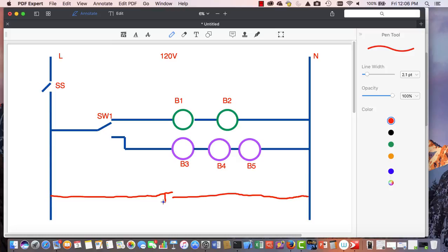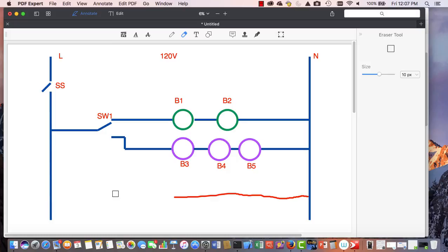that would be a direct short circuit, because I have a switch, but the moment that thermostat closes, I would now have an uncontrolled path of power from line to neutral. So you can't do that. Let's just get rid of that so we don't get ourselves confused. So that is a basic schematic diagram that's drawn from a paragraph, or a sentence, that tells you how something should work.